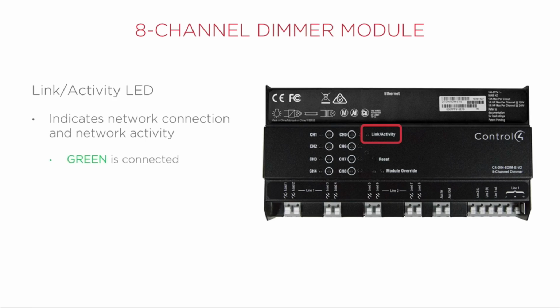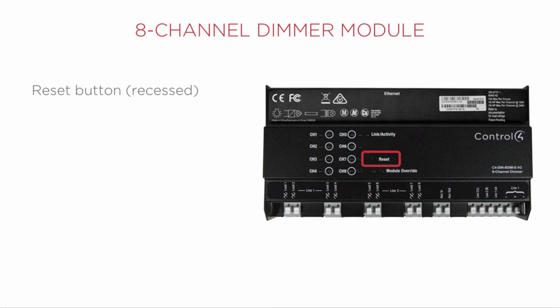The link activity LED indicates network connection and network activity. If the LED is green, the module is network connected, and if the LED is orange, there is activity on the network through the module. There is a recessed reset button. If that button is pressed, the module will reboot. If the button is pressed and held, it will reset the module to factory defaults.